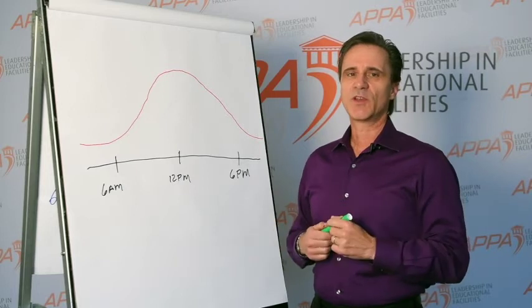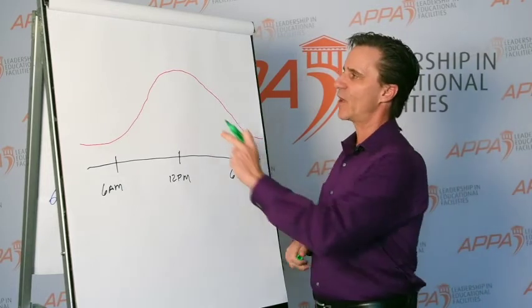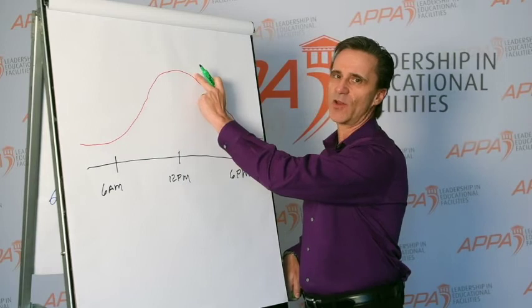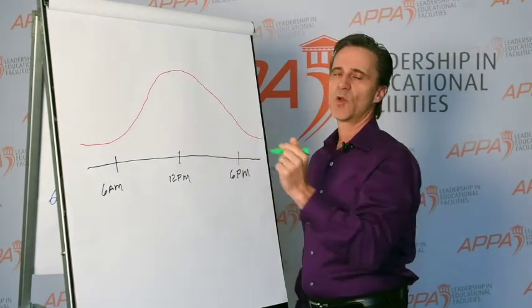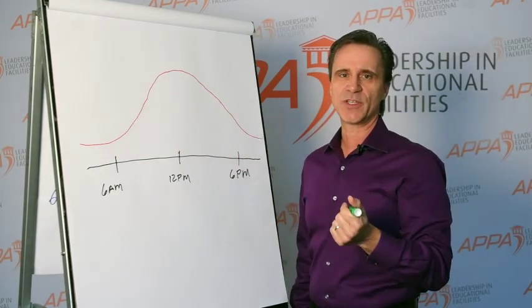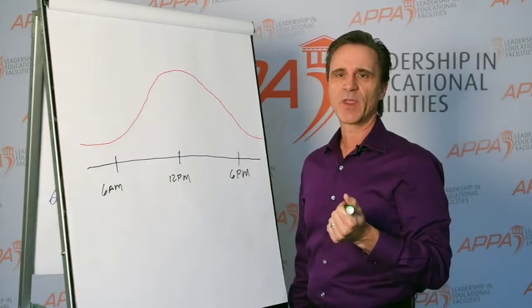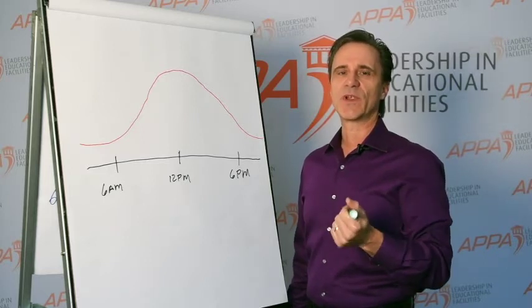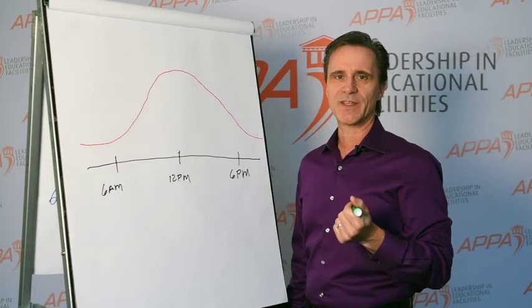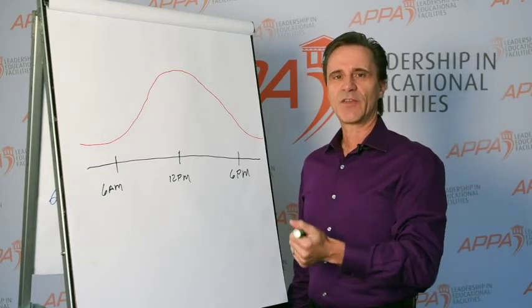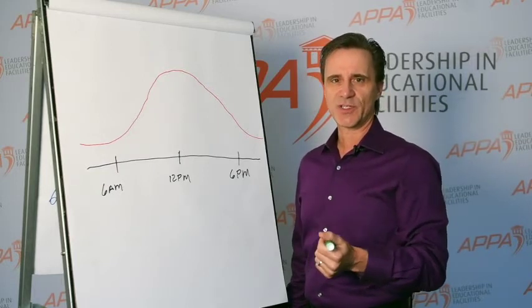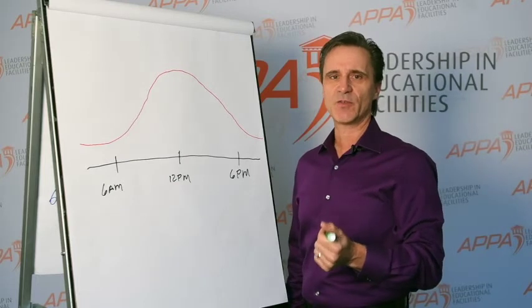In the daytime, instead of running chillers to satisfy our cooling demand on campus, we can deploy the thermal energy we have stored in our storage tanks. This allows us to reduce the number of chillers we're running in the daytime. Running fewer chillers means using less electricity, demanding less electricity from the utility.